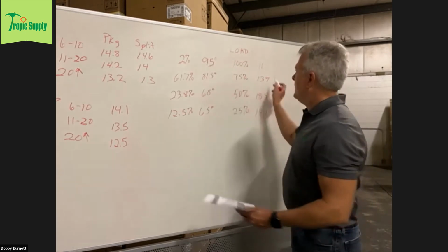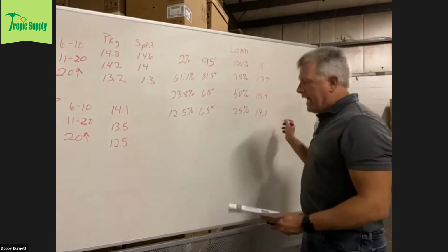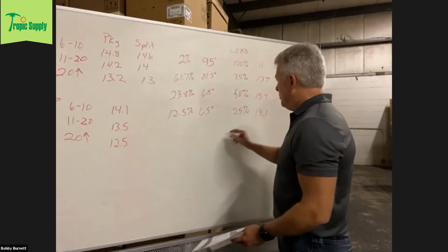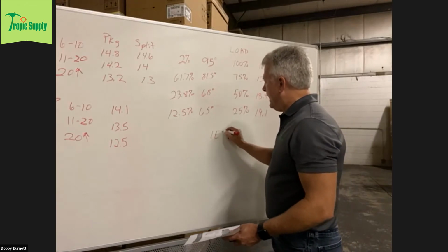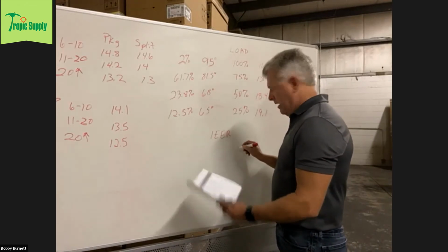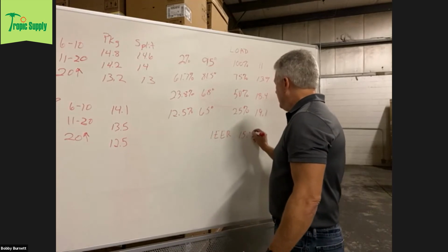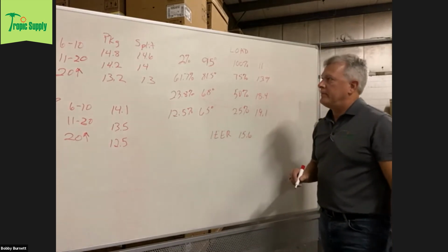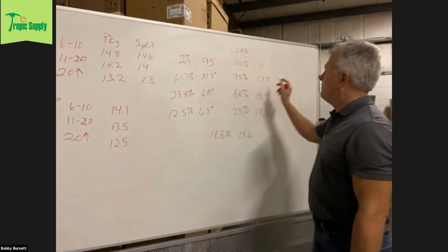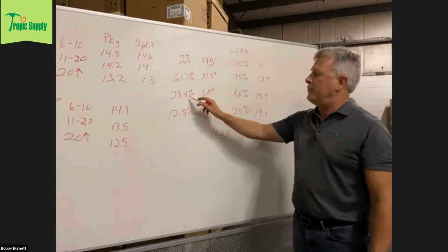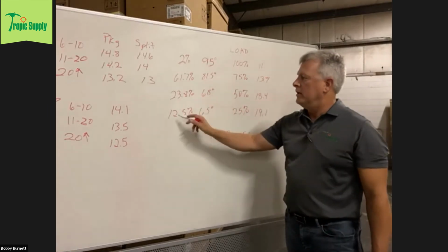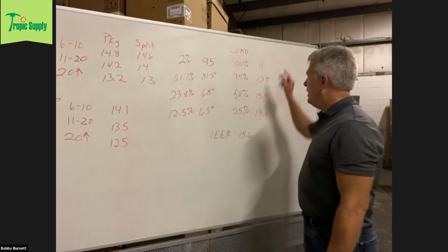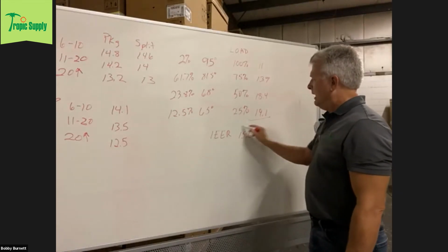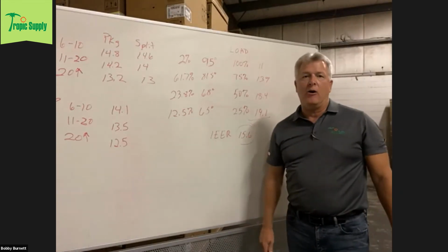Okay. Then they multiply that times that, that times that, that times that, that times that, add it all up together, and you would end up on this unit with an IEER of 15.6. Okay. So again, 2% of 11, 61.7% of 13.7, 23.8% of 19.4, 12.5% of 19.1. Add those all up together, and that's your new IEER rating.